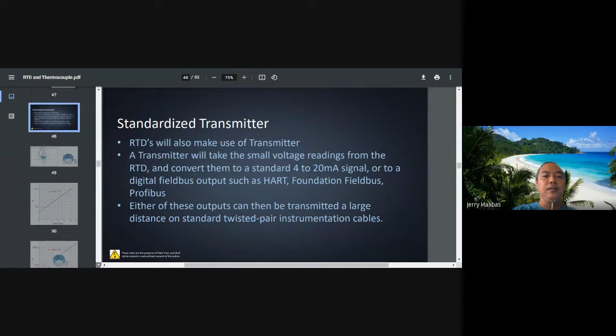In the example, the temperature transmitter, you notice that this blue one is the transmitter. Okay? What is a transmitter? Now, let us say you want to convert the current output, the 4 to 20 milliamps output, to temperature. So you can compute it mathematically. We know that its response is linear, so we draw a straight line.